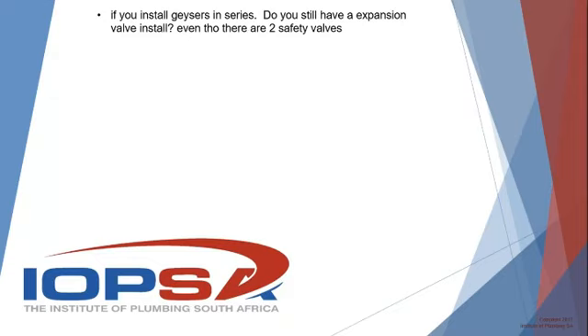So no. Doesn't matter how many geysers, each geyser must have its own safety valve, and then there must still be an expansion valve for that installation. Yeah, quite right. I think I just read that question as well. I think there's a confusion. An expansion valve is not a safety valve or TP valve. They are two different types of valve and have two different functions. The one works on expansion, and the other one works on temperature. So just be aware of that, and I think that is what this person has indicated here. I think he's confused the two.